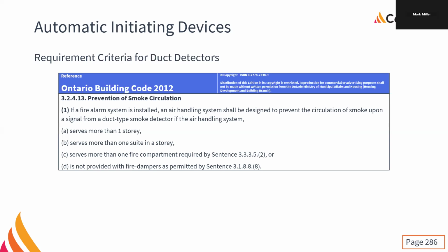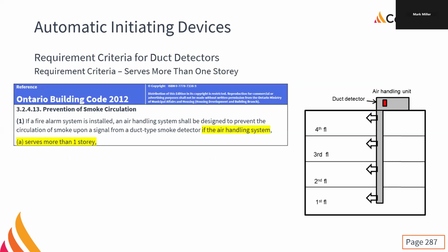Right. So if we've got one air handling unit that's doing all 4 floors, the giant air handling units that we see in colleges, universities, and hospitals, it's going to get duct smoke detectors because, well, if it starts to throw smoke, it's going to be throwing smoke all over the place, and we're not going to know where the fire's coming from. Right, so we're going to want to shut it down.